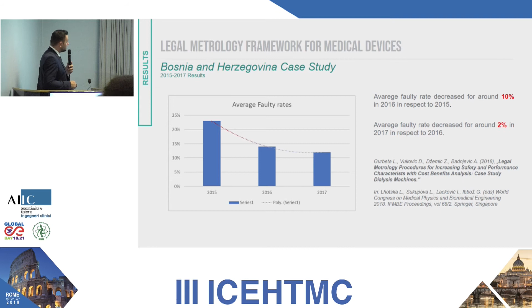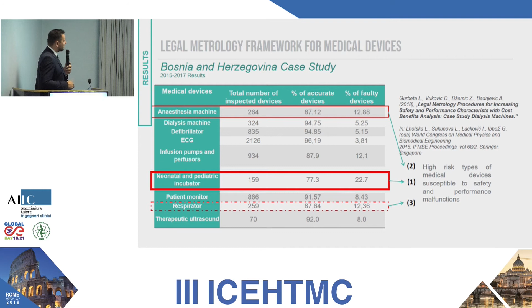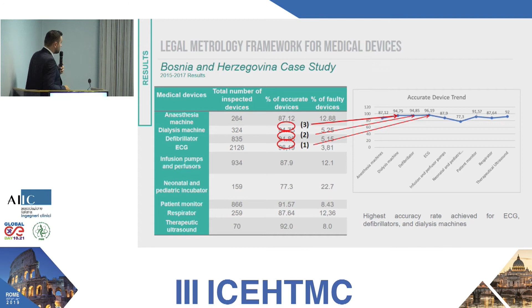For example, first, this is showing the increase in the number of inspected devices per year from 2015 to 2017. This is the decrease of the average faulty rates in medical devices from year to year. Here you can see at the beginning what the faulty devices and percentages were. For example, the worst were the incubators for babies and anesthesia machines, which are very critical devices. It was pretty good, for example, for the dialysis machines, defibrillators, and ECG. This is now for all of them separately. I will skip those things. You can find all that in different published articles.